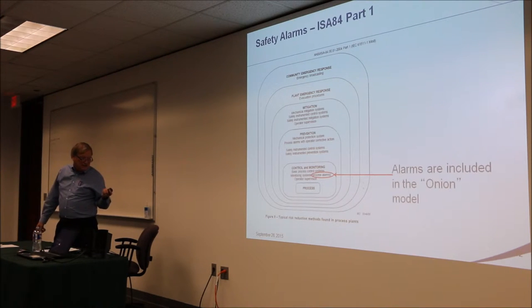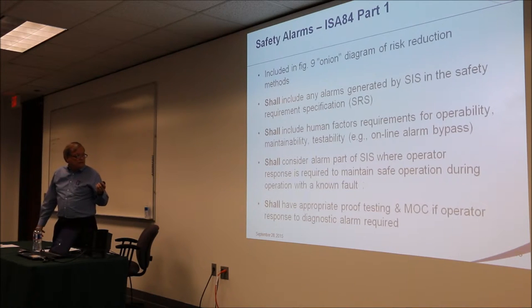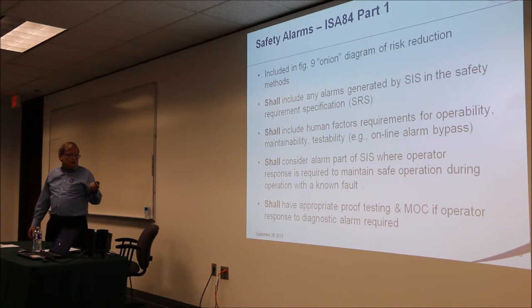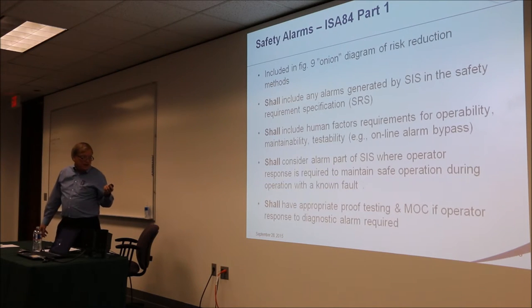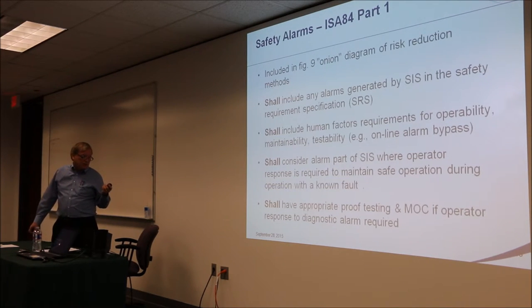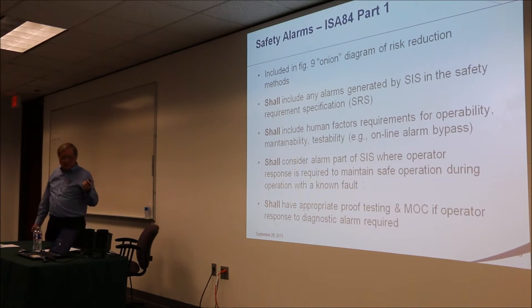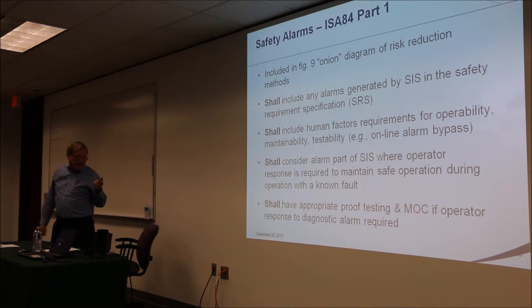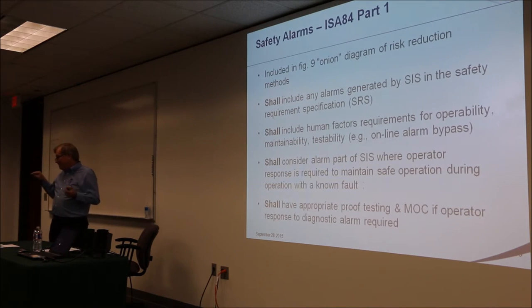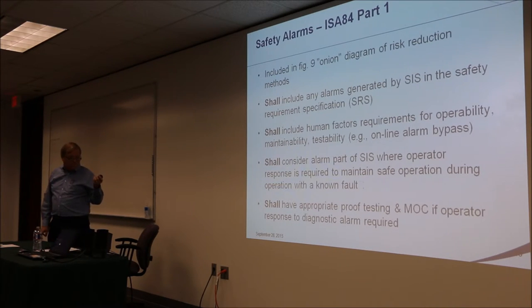In the typical risk reduction methods shown in the so-called onion model, alarms are clearly identified as one of the methods. Some of the shall statements and requirements include: alarms generated by the SIS shall be in the SRS; human factors requirements for operability, maintainability, and testability must be included; and you shall consider an alarm part of the SIS if the operator must respond to maintain safety — for example, if an alarm indicates an operator has to hit an ESD. In that case it needs appropriate proof testing and MOC.